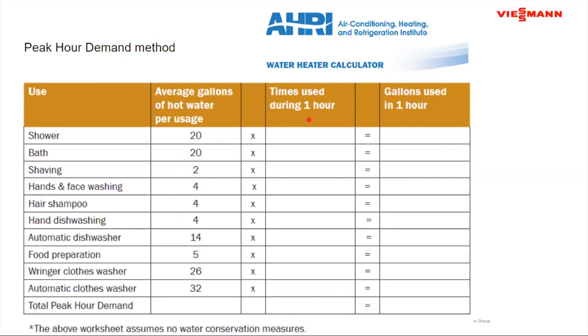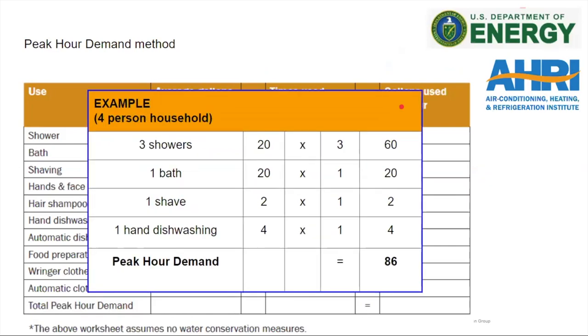So this four bedroom house, how many showers are they going to take in the peak hour? How many baths are they going to take? You really have to do a survey of how hot water is being used in that house. And then we simply multiply it and add it up to get our total demand down here. So for instance, let's say we talked with the homeowners and they said, you know what? During our peak time, there's going to be three showers, and three showers are going to use 20 gallons each, that gives me 60. During that peak time, one of those people is going to be taking a bath, that's another 20 gallons, so we add that over here.